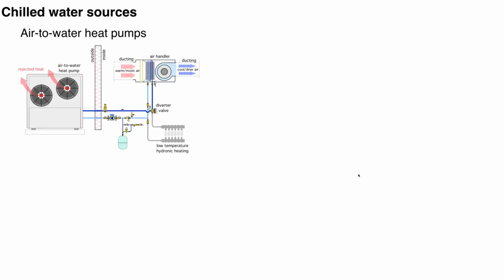Let's talk about chill water sources. We're going to focus a little bit more today on air-to-water heat pumps. We've done several past Coffee with Caleffi presentations dealing with the details. If you want more information on air-to-water heat pumps in general, Hydronics number 27 and number 30 would be good reference issues to look at. But an air-to-water heat pump system, as I mentioned earlier, is a reversible refrigeration system, so it can provide chilled fluid. Now, the fluid is going to be a mixture of water and antifreeze in most applications in North America because we have to protect the system in the winter from freezing.